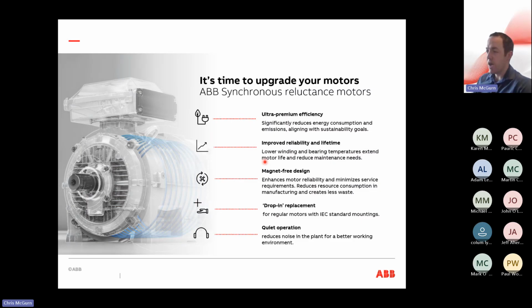So this is our IE5 motor. It's ultra premium efficiency. It meets IE5 requirements, even though the regulations currently only go to IE4. What is IE5? Generally, the steps in the IE regulations between IE1, IE2, IE3, IE4, each one of those steps has a 20% reduction in losses across the motor. So IE5 will have 20% less losses than an IE4, and an IE4 in turn will have 20% less losses than an IE3. So this IE5 is at the forefront of our efficiency technology, and they offer improved reliability, improved lifetime. What I was talking about earlier, because they are more efficient, because they are running at lower temperatures.